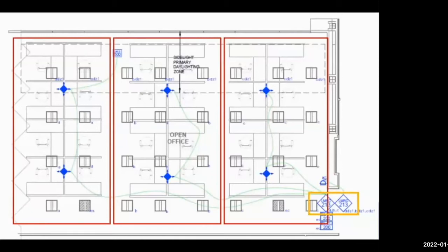And you also notice inside this space that we have some emergency lighting. Many codes now are requiring that the emergency lighting also be shut off with the other lighting inside the space, and therefore oftentimes will require some control mechanism like an emergency control unit. Usually it's a 924 unit that will allow these lights to switch with the controls, yet in the event of a power failure the lights would be able to be forced all the way on.